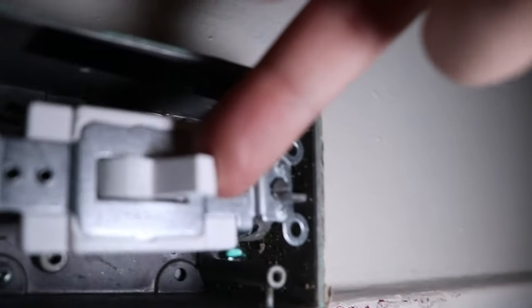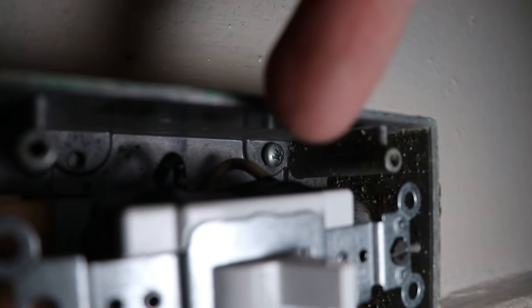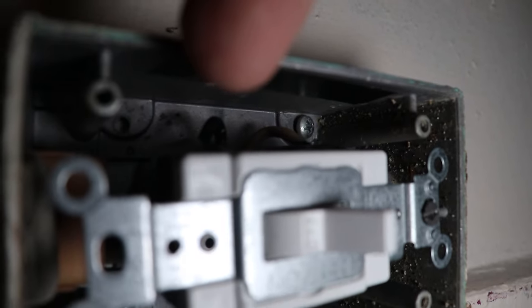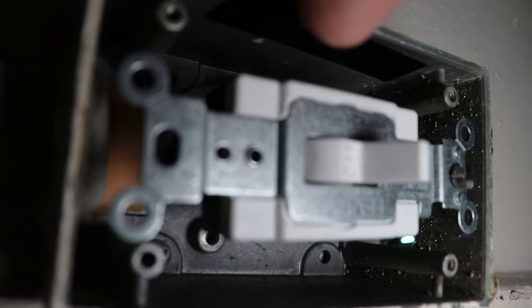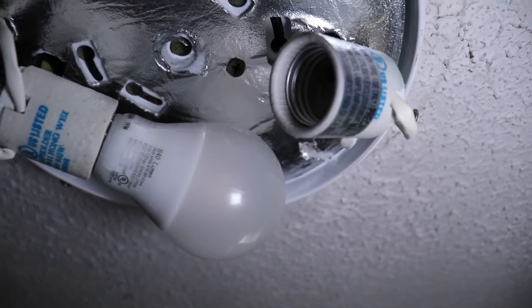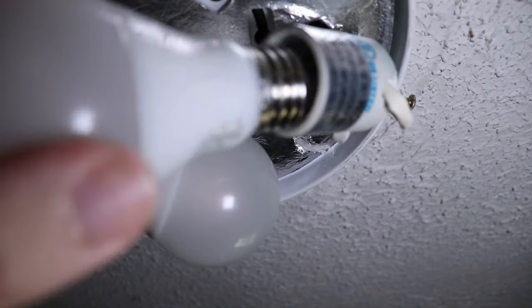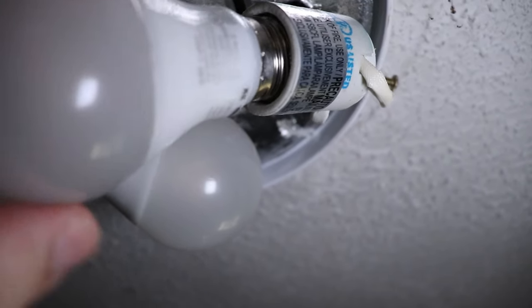because when you do flip this switch, it's going to be power coming from the panel to power going to the fixture. There are no neutrals in here. And as you can see, even though there is a ground screw, there is no ground. That's what that green screw is in there. Remember that once you've installed your light fixture, put your bulbs back.